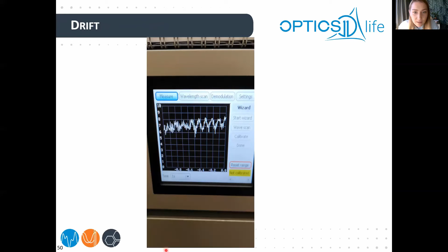Does this work? Yes. So here I submerge the probe in the medium and just observe the signal in the measure window. And now you can see that the signal is not stable. It's just going up and down through the fringes. So it's going up and then down. And this is the drift. So you cannot measure while the probe is drifting.